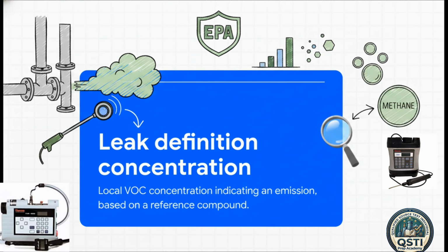But wait, before we start measuring anything, we need to know our exact threshold for danger. What actually counts as a leak? That's defined by a critical metric called the leak definition concentration. The EPA doesn't just vaguely post and say find a leak. No, they specify a precise parts per million number based on a reference compound, like methane. So, if the local concentration right at the surface of a valve hits that specific number on our calibrated meter, boom, we officially have a leak on our hands.